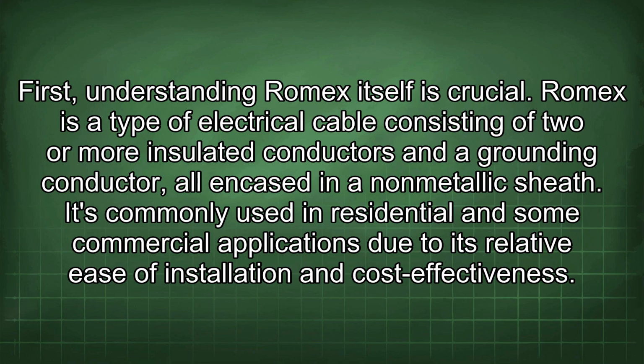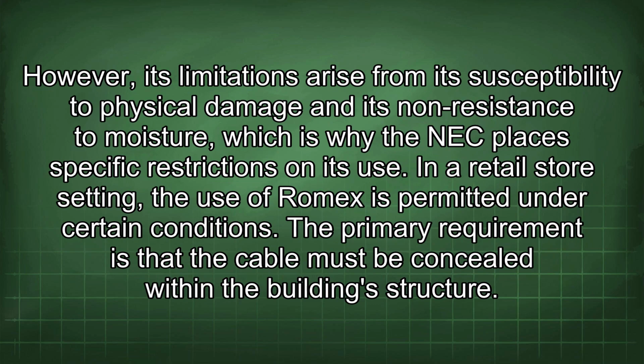Romex is a type of electrical cable consisting of two or more insulated conductors and a grounding conductor, all encased in a non-metallic sheath. It's commonly used in residential and some commercial applications due to its relative ease of installation and cost-effectiveness. However, its limitations arise from its susceptibility to physical damage and its non-resistance to moisture, which is why the NEC places specific restrictions on its use.